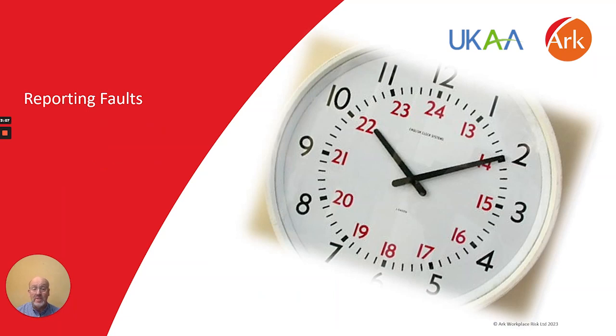In addition to the checks being made, responsible persons are also required under the regulations to take all necessary steps to fix and report any damage they discover to the fire and rescue services. Responsible persons will not have to inform their local fire and rescue service immediately regarding a relevant fault if they believe that it can be resolved within a 24 hour period. If the issue cannot be resolved in that 24 hours, then they must report it to the fire and rescue service as soon as practicable. The responsible person is also required to arrange for the issue to be fixed and then report that back to the fire and rescue service once it's been resolved.